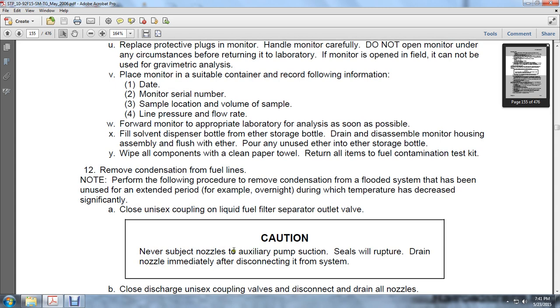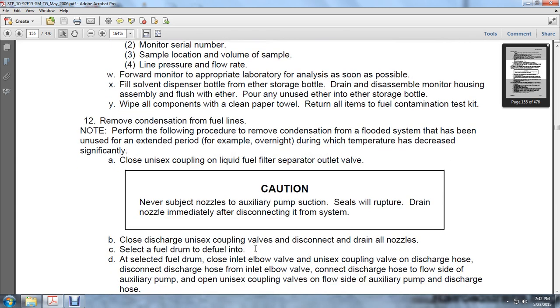Never subject the nozzles to auxiliary pump suction. Seals may rupture. Drain the nozzle immediately after disconnecting it from the system. Close the discharge unisex coupling valves and disconnect and drain all nozzles. Select the fuel drum to defuel into. Select the defuel drum, close the inlet elbow valve, the unisex coupling valve, and the discharge hose.